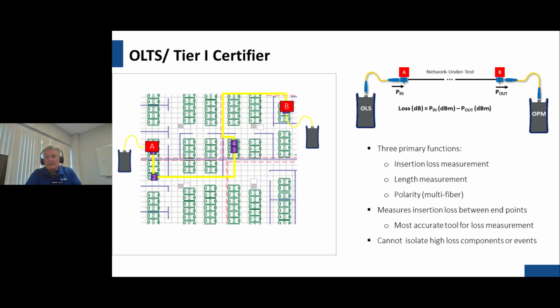So the OLTS is really the most accurate tool for measurement, and that's really why cabling vendors would require this for their tier one test of insertion loss. The disadvantage, as we said, is that if there was a high loss—if it came back beyond the insertion loss limit—we wouldn't really know what was causing that high loss, whether it was a bad connector. Typically these aren't spliced, but it could be a splice in an outside plant situation. So that's really where we'd rely on the OTDR to do that isolation.